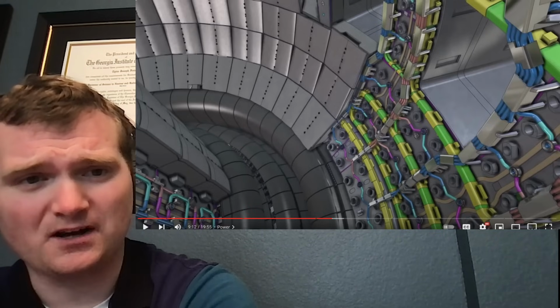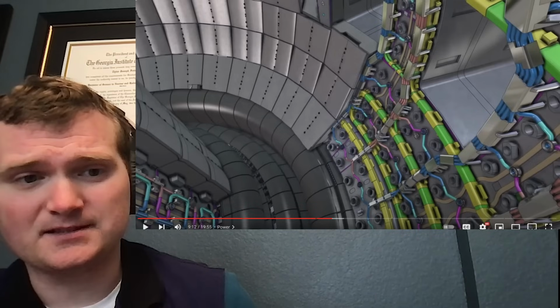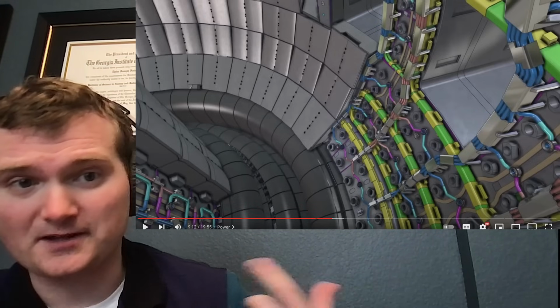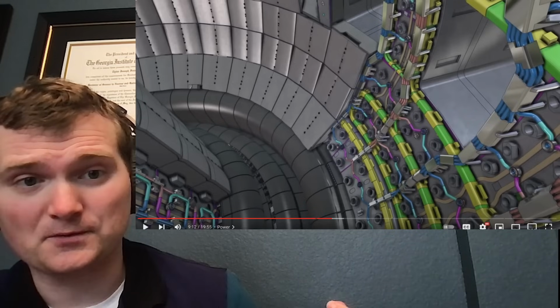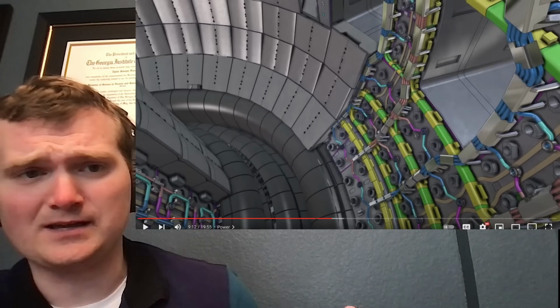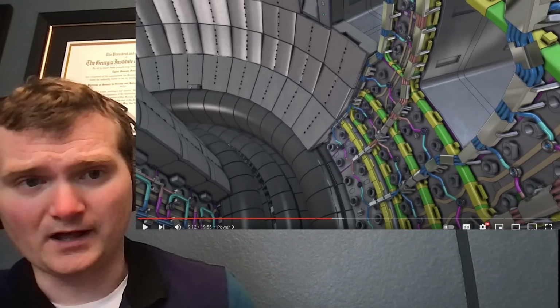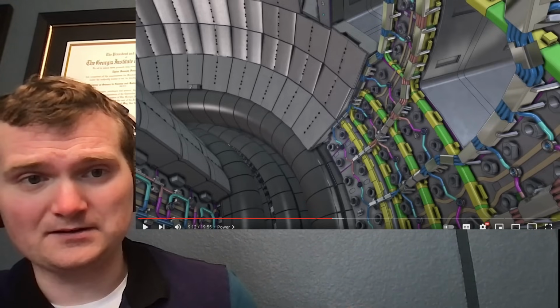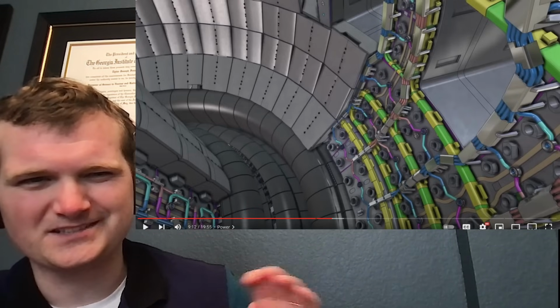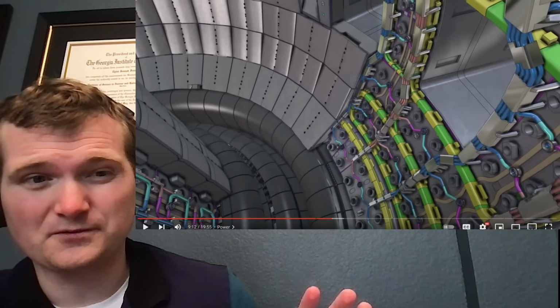In fact, when the reactor's offline, it gets the 30 to 50 megawatts for house loads like reactor coolant pumps from the grid. And then once it starts up, it would have the option to either power its own house loads. You could cross connect it from the other unit, though a lot of times it's typically left from the grid, just because that's a bit of an easier configuration.